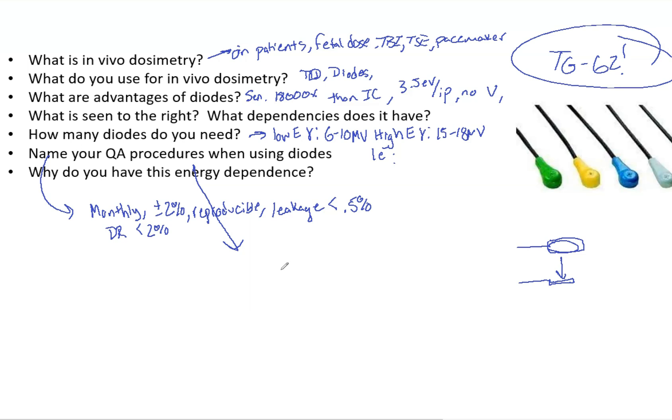There's also an angular dependence due to just the different transmission thicknesses and backscatters, which is why you need to use a cylindrical one for photons and a flat one for electrons. Also field size, there's a field size dependence. So the sensitivity increases with increasing field size.